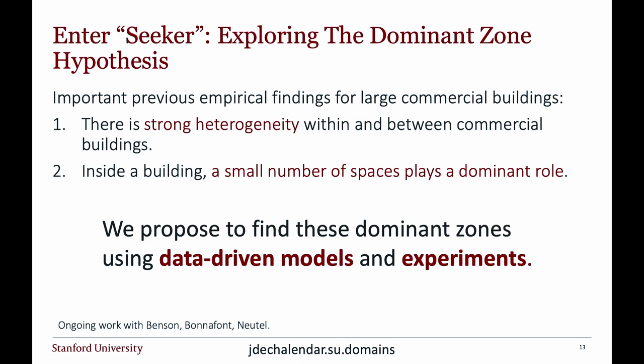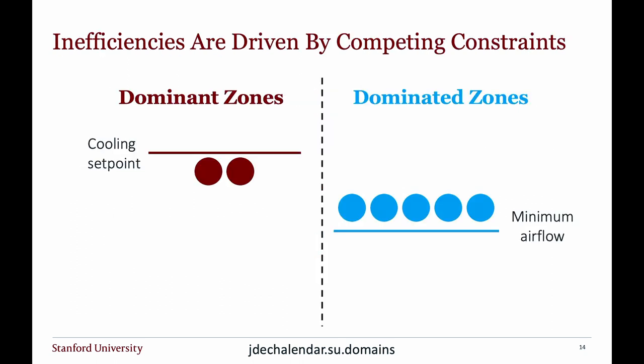My summary schematic here is there's a small number of zones that are at their cooling set point, so they're always too hot and trying to cool down. They're making requests to the central system to get colder or more air. Then there's another set of zones, the dominated zones in blue, that are at their minimum airflow. Each zone has two sets of constraints: a dead band for heating and cooling temperature, and a dead band for ventilation. A lot of these zones are at minimum airflow, and that's why they're overcooled, because the temperature is central, there's one temperature common to everyone, but airflow is the part you control.